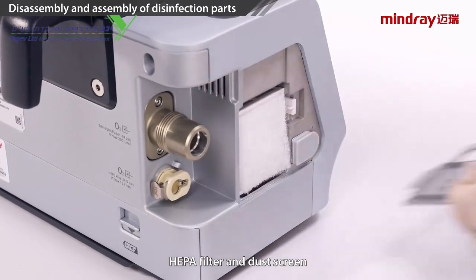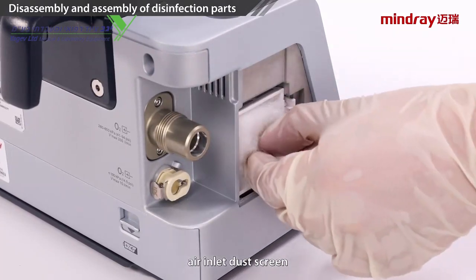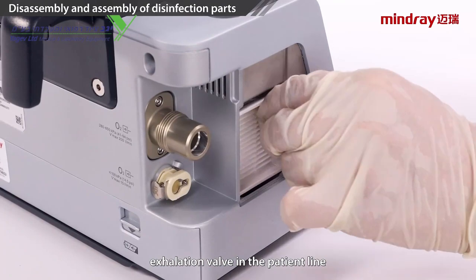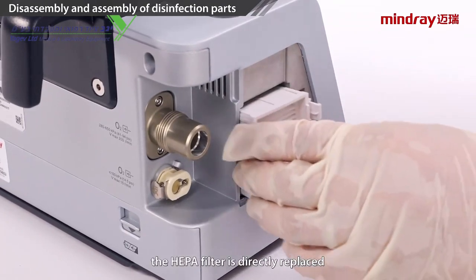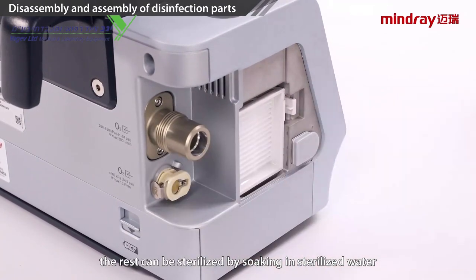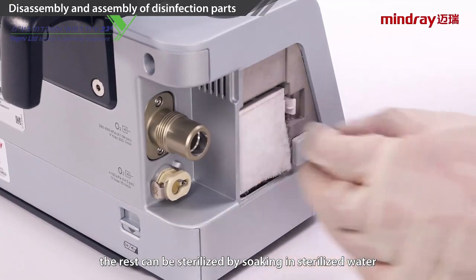HEPA filter and dust screen, air inlet dust screen, exhalation valve in a patient line. The HEPA filter is directly replaced, the rest can be sterilized by soaking in sterilized water.